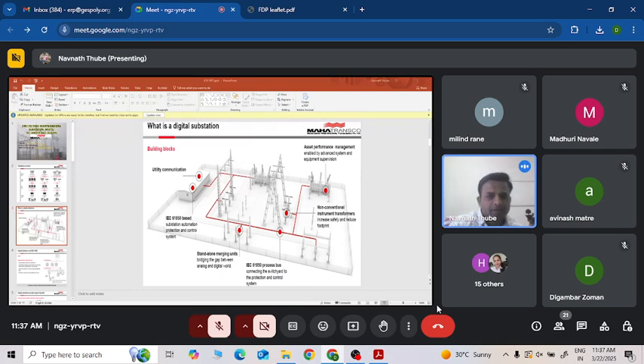Switchgear control unit, main use case: interface input-output signals from primary apparatus for use at bay and station level. It reduces cost in the switchyard by optimizing copper cable and communicating via the same IEC protocol. This is our regular relay panel in the control room. The process bus is connected between the SAM input output unit and IEDs or relay panel through fiber optic cable only. The station bus is connected between the IED or relay panel and the SCADA system through fiber optic. It transfers data both ways. All measuring and control signals are communicated through fiber optic cable. Relays are used for all types of protection and measuring, as in conventional substations.